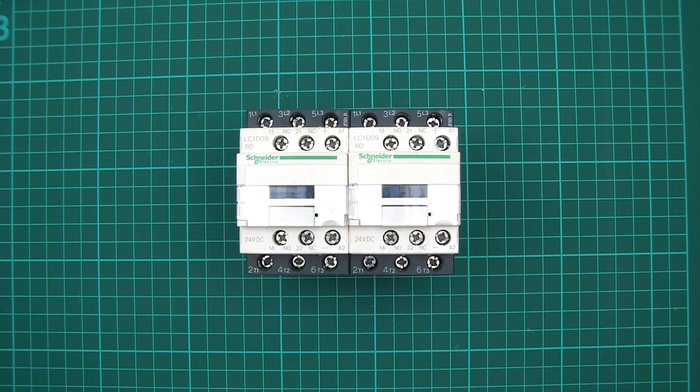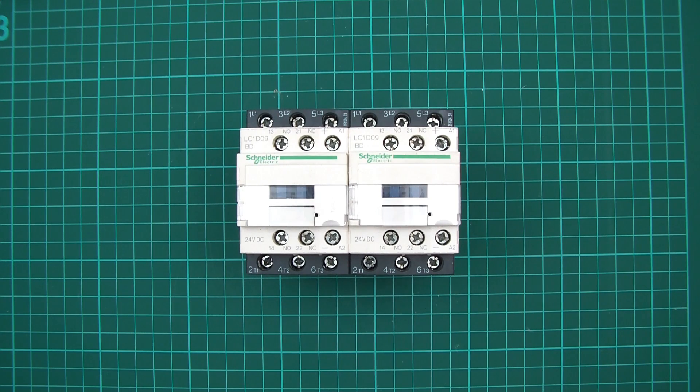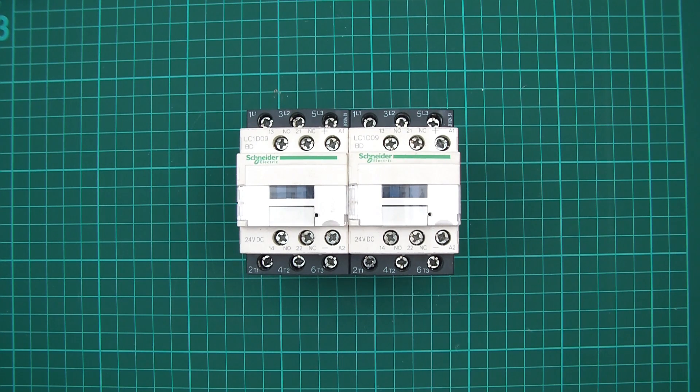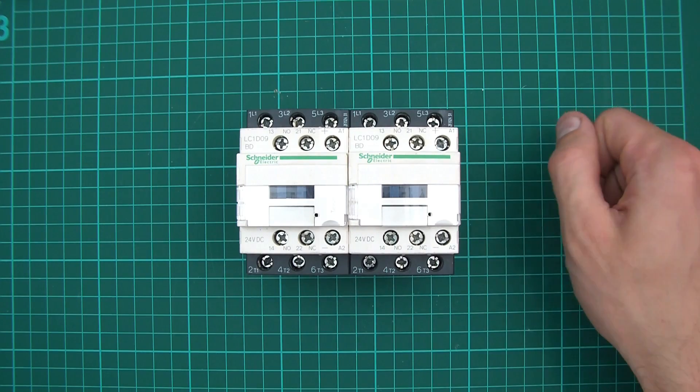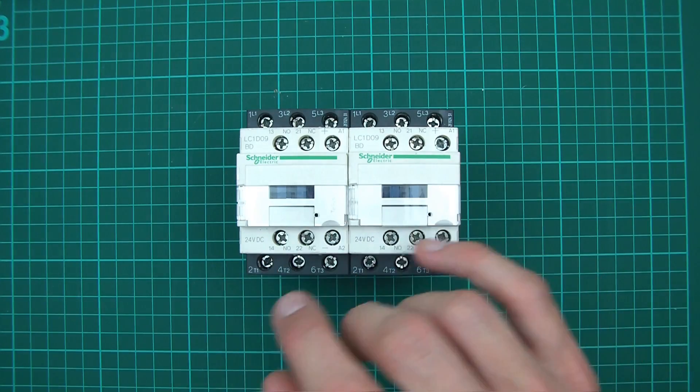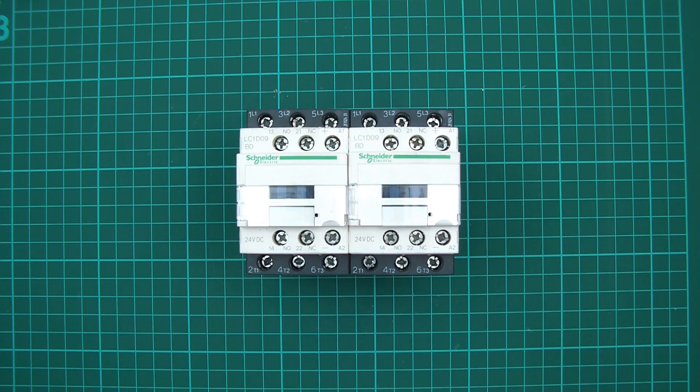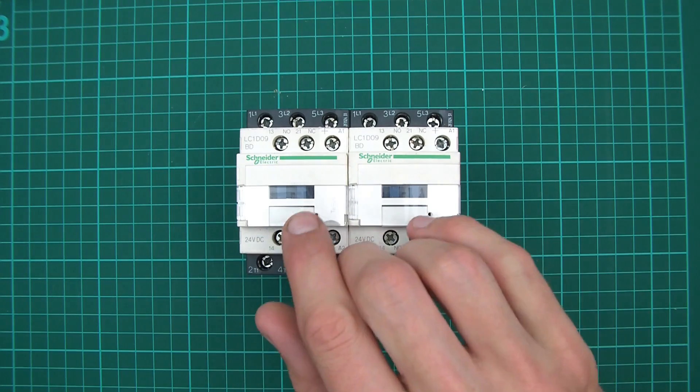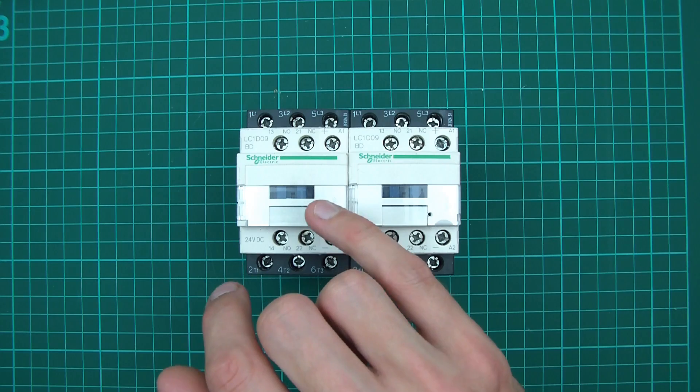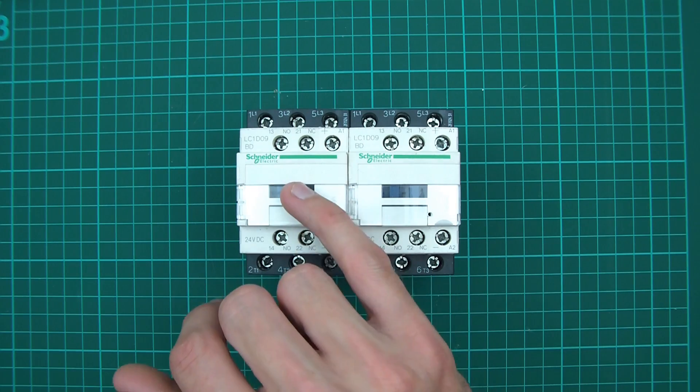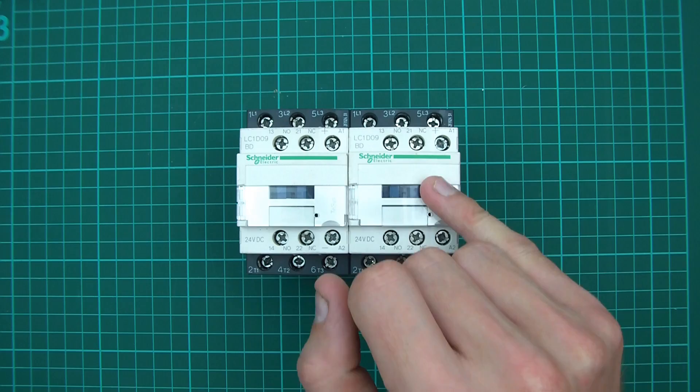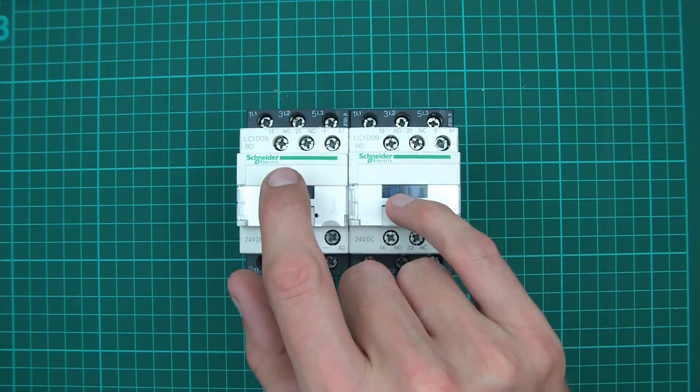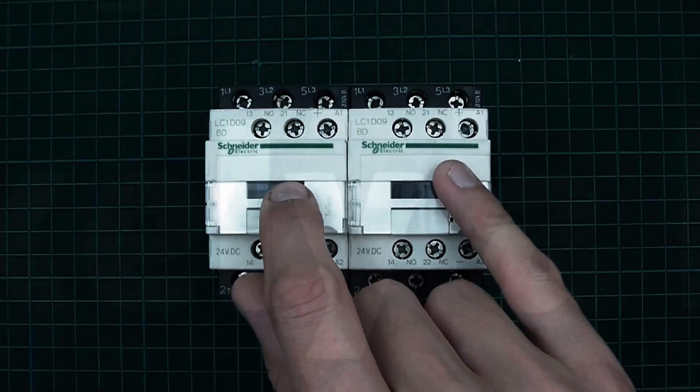I called this an automatic transfer switch or automatic changeover switch, and what do I mean by automatic? There's no manual switch to switch over from one to the other. There are configurations whereby you can set this thing up to go off one power source and then automatically change over to the other power source when the coil is not powered on the original one.